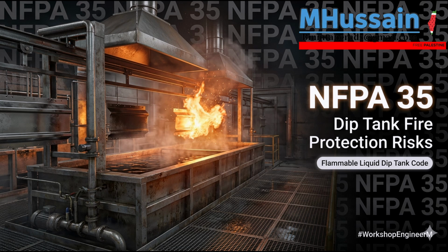Because as the liquid falls, gravity breaks the solid stream apart into thousands of individual droplets. Exactly. And as those thousands of droplets fall rapidly through the air, the friction generates and rapidly accumulates a massive static charge. It is essentially a high-voltage static electric waterfall inside the tank. So how do you physically prevent that? The standard mandates the use of engineered fill pipes that extend all the way down to the bottom of the receiving tank. Instead of splashing from the top, you pipe the liquid down so it gently fills the tank from the bottom up.